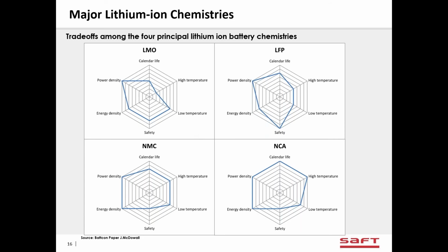Some of the differences between all the different chemistries that are out there: there's always trade-offs. Why do they make all those different chemistries? Well, if you're trying to maximize energy density and power density, you're going to go with metal oxides. If you're trying to maximize safety, you're going to go with either iron phosphate or lithium titanate. I don't have titanate on this graph, but you can see here that the safety rating of iron phosphate is higher than the others. And we're going to mostly consider here what happens during thermal runaway.